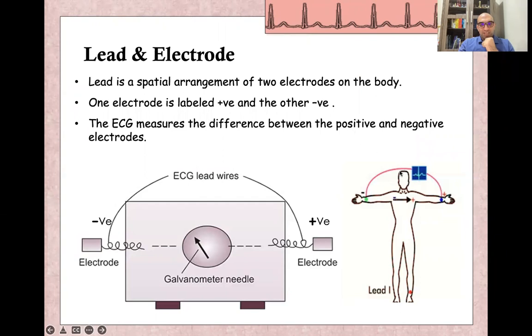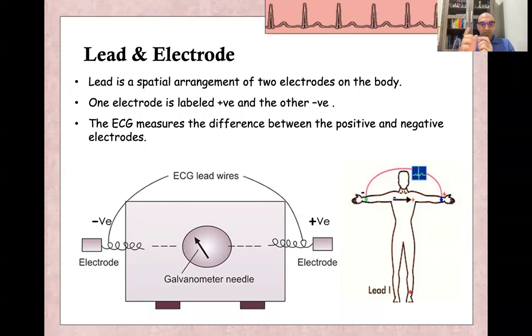A lead is a spatial arrangement of two electrodes. One electrode is labeled negative, and the other is labeled positive. The ECG machine works like a galvanometer — it measures the difference between the positive and negative electrodes. One galvanometer equals one lead, so a 12-lead ECG requires 12 galvanometers.